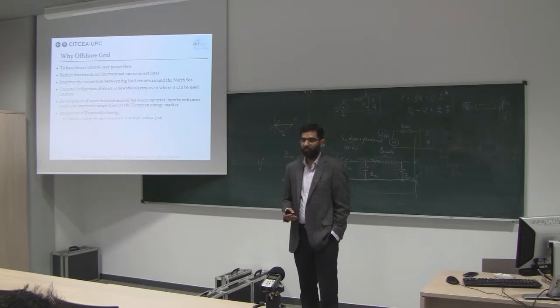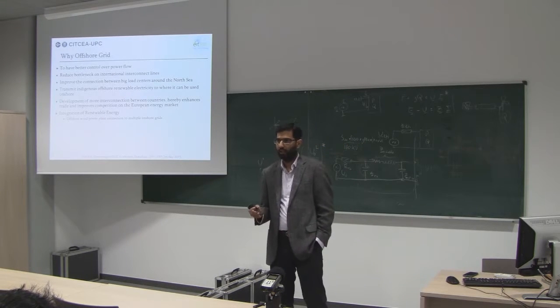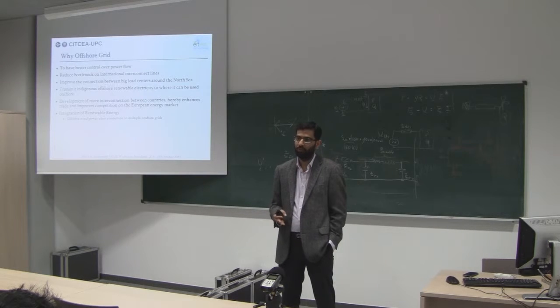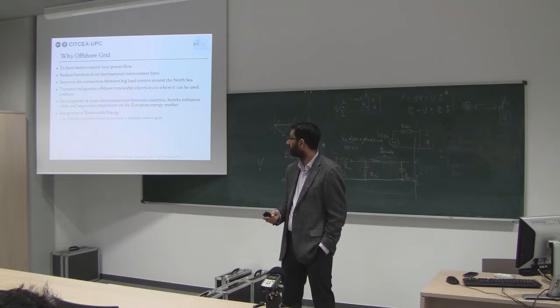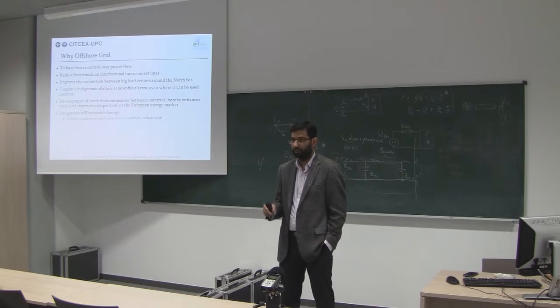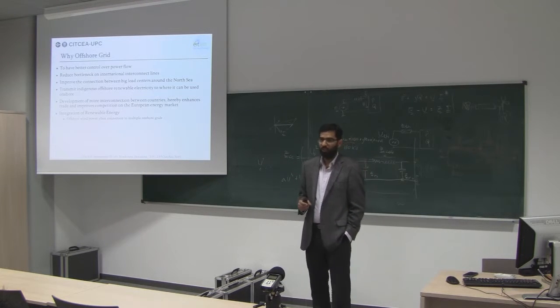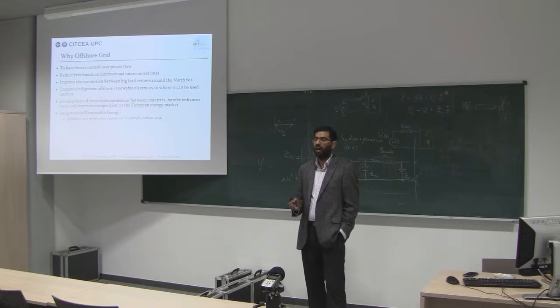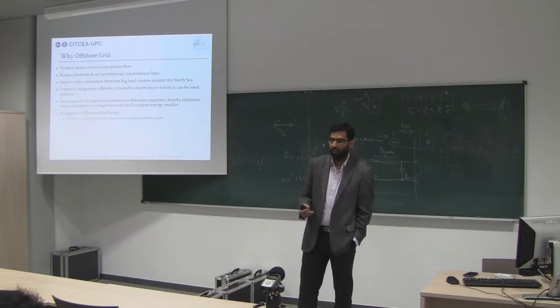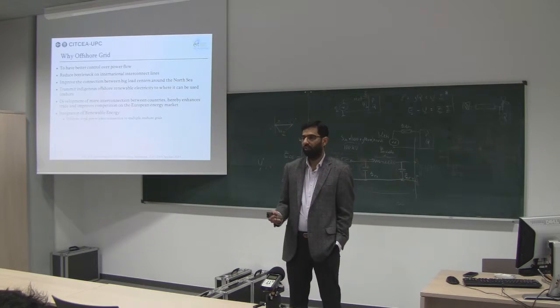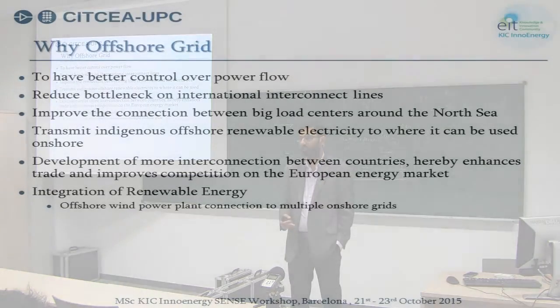In HVDC we use voltage source converters. There are two concepts: line commutated converter and voltage source converter—I'll show the difference in a couple of slides. For voltage source converters, the technology we have isn't yet available at high power. When building a transmission line as an interconnector, you need high capability to transfer power, because it's essentially a trade and you're not going to remake it every year or two. So the technology is limited by converter size, and it's not cheap compared to AC transmission systems.